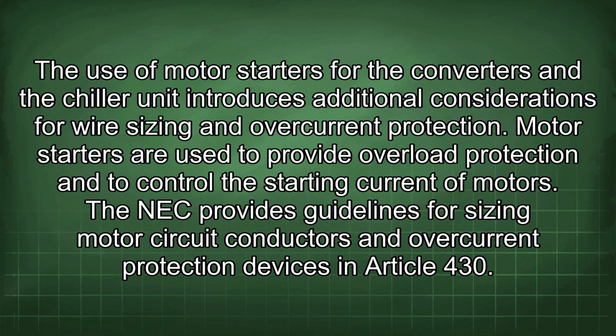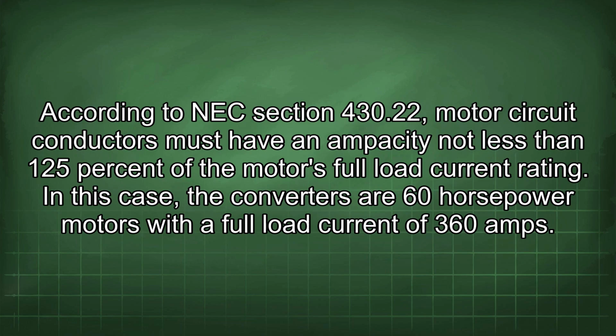The use of motor starters for the converters and the chiller unit introduces additional considerations for wire sizing and overcurrent protection. Motor starters are used to provide overload protection and to control the starting current of motors. The NEC provides guidelines for sizing motor circuit conductors and overcurrent protection devices in Article 430. According to NEC Section 430.22, motor circuit conductors must have an ampacity not less than 125% of the motor's full load current rating.